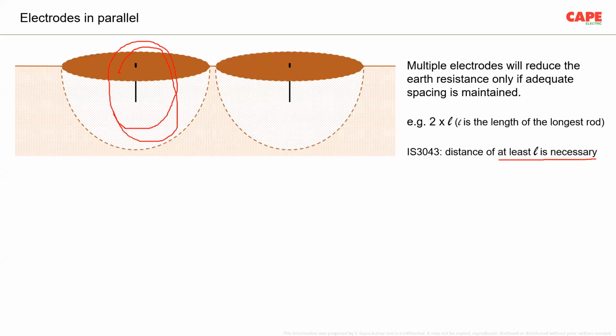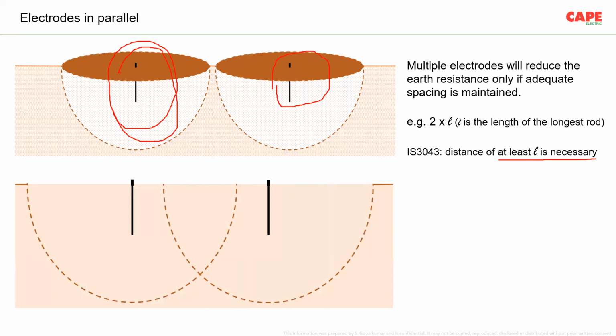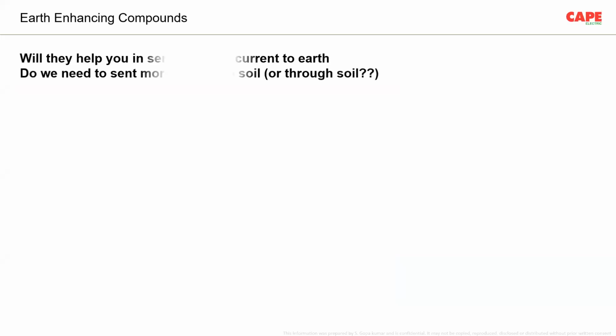And if this separation is made, at least imagine this one is the first one where I am drawing. If this is the earth electrode of the transformer, the second one is made, the neutral earthing at the secondary side of the transformer is made at the first post, at least 10 to 15 meters away. So higher resistance or the higher distance is making a better value. Otherwise, multiple earth electrodes will not reduce the earth resistance if they are placed closer. But in most electrical installations, if we go and visit practically, earth electrodes are connected quite nearby. 3 meter rods connected in every 3 meters, or put in every 1 meter, not 3 meters, sorry, 1 meter.